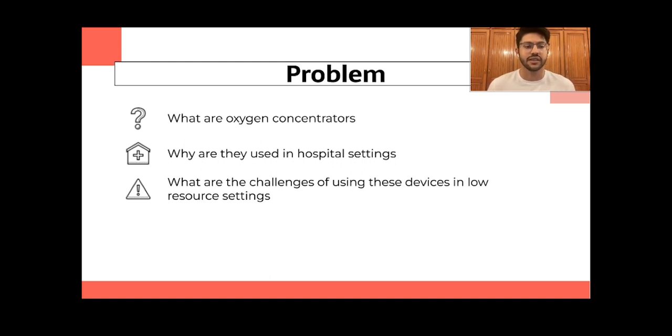For example, sometimes the devices coming in might be close to end of life because these devices aren't brand new and instead have been donated from some cause. Also, because of regular mechanical wear and tear, these devices might not be running as efficiently as expected. All of this can lead to the devices providing less than the desired 90 to 95% oxygen concentration. Another factor in this degradation could be dust, dirt, and debris. So, it is essential that there should be devices that can monitor the performance of an oxygen concentrator and give us a reading for what the oxygen concentration is.